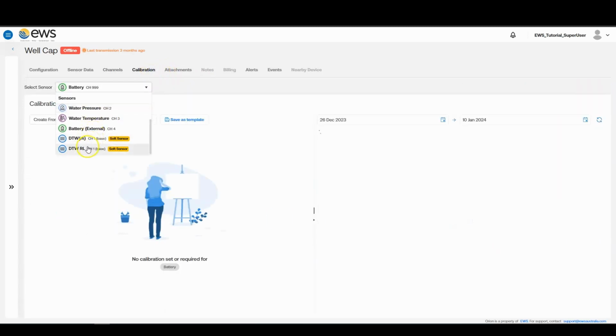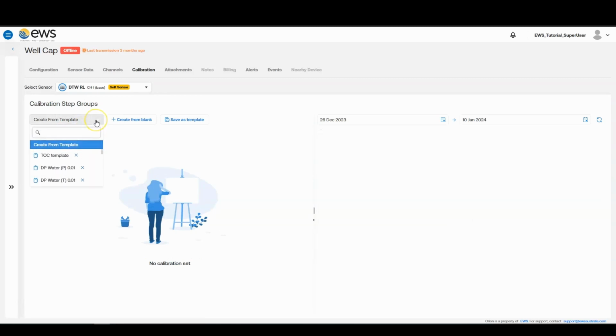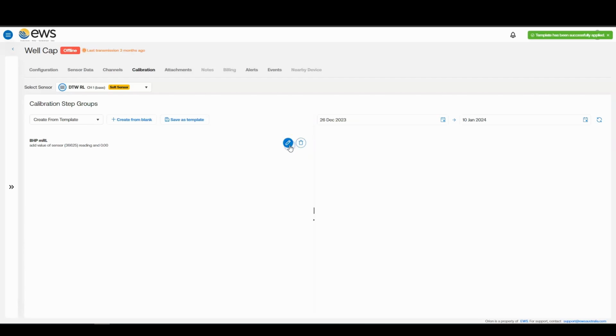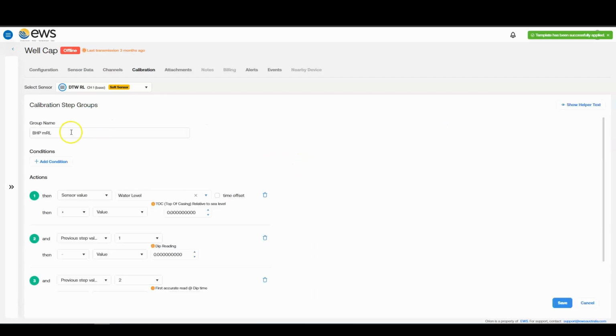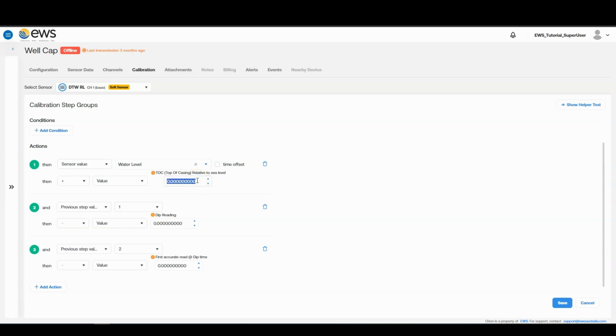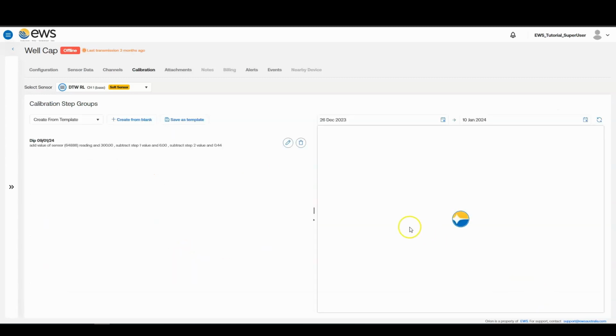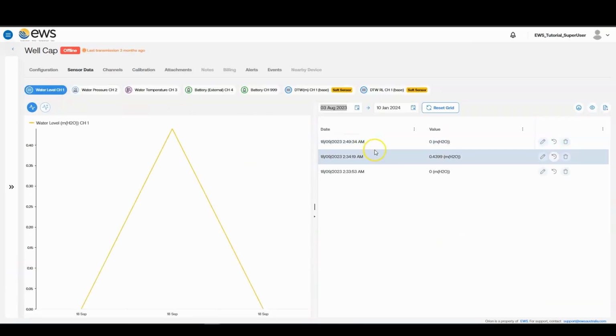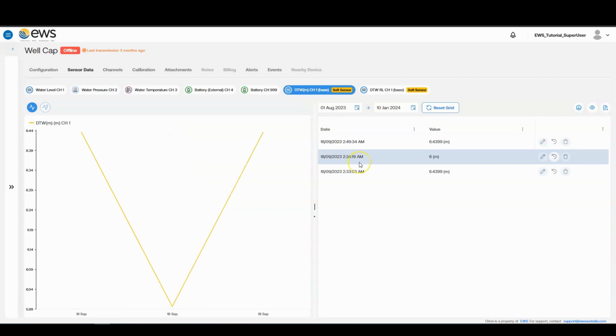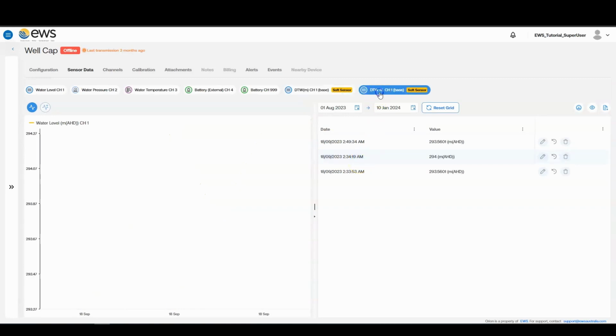Select the depth to water RL sensor, and then we'll add from a new template our MRL conversion. We can rename our calibration to the date of the dip measurement. Insert our surveyed datum, typically the top of casing in relation to sea level, and then the dip reading and sensor reading, then hit save. Finally, we can return to the sensor data and ensure all our calibrations have taken effect and are showing the correct results.